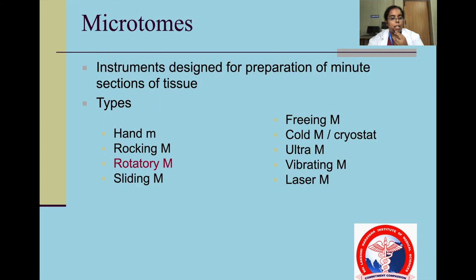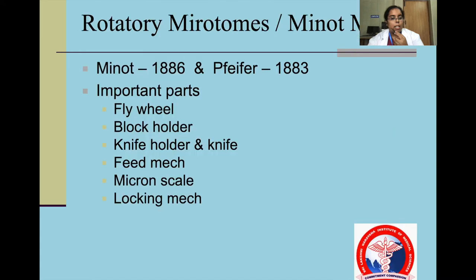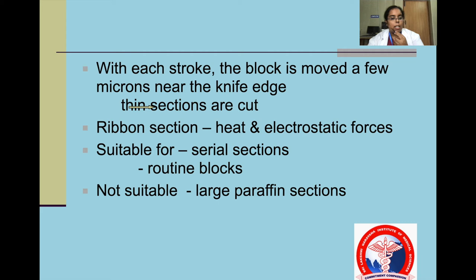Microtomes are designed for preparation of minute sections of tissue. Types include hand, rocking, rotary and sliding. In a rotary microtome, the important parts are a flywheel, block holder, knife holder, feed mechanism, micron scale and locking mechanism. With each stroke the block is moved a few microns near the knife edge to give a thin section. Ribbon sections form because of heat and electrostatic forces. These are suitable for serial sections and routine blocks but not suitable for large paraffin sections.